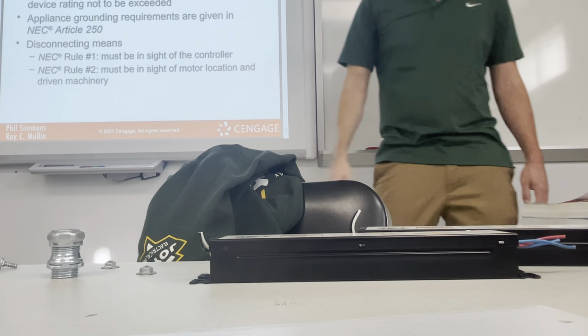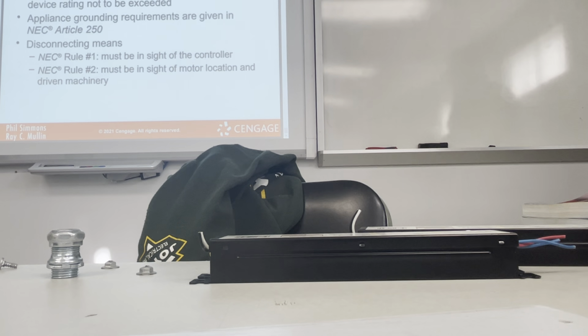All right, let me do the summary. Appliance maximum size and overcurrent protective device rating not to be exceeded. Appliance grounding requirements are given in NEC Article 250. Disconnecting means, NEC Rule Number 1, must be in sight of the controller. NEC Rule Number 2, must be in sight of the motor location and driven machinery.